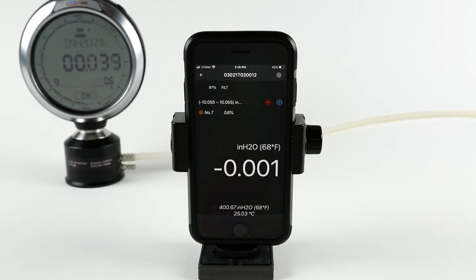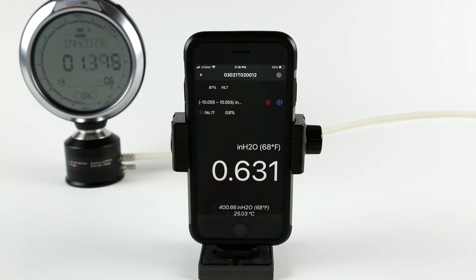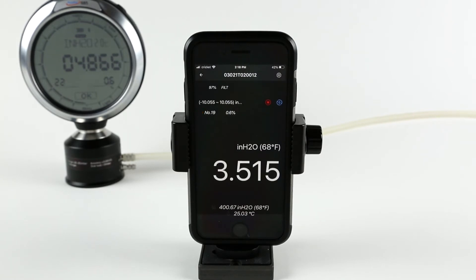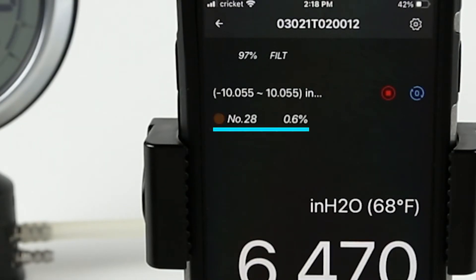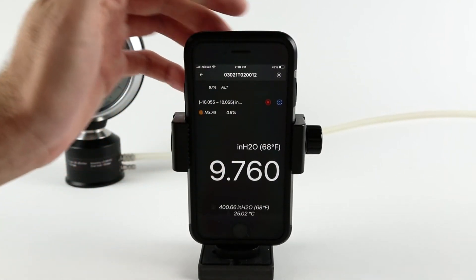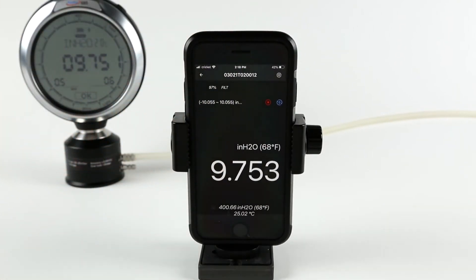You can easily select the internal temperature and barometer pressure to be recorded as well. Select the play button to start the logging session. Once a log session is underway, Additel Link displays a count of the number of recorded readings and a percentage of memory available. To end the log session, simply press the stop icon in the app.